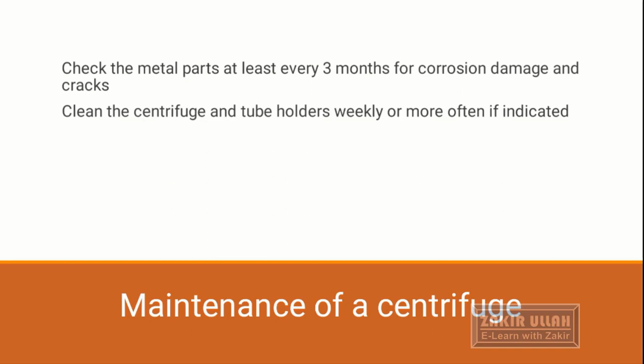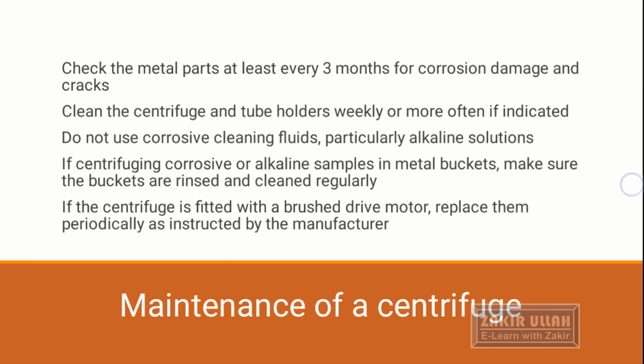Do not use corrosive cleaning fluids, particularly alkaline solutions, because certain parts of the centrifuge are sensitive to corrosive fluids, so they can be damaged. Therefore we have to check whether these solutions contain any alkalis or are corrosive or not. So we have to take care of these things. If centrifuging corrosive or alkaline samples in metal buckets, we have to make sure that the buckets are rinsed with clear water and cleaned regularly. And if the centrifuge is fitted with a brush driver, replace the brushes periodically as instructed by the manufacturer. So these are the different aspects of maintenance, care, and troubleshooting of the centrifuge.